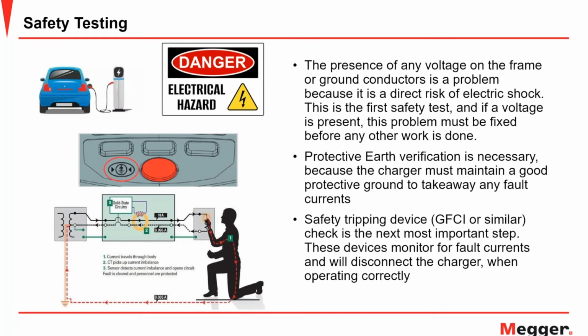Now, in itself, that protective earth verification is important, but then another layer of safety is the safety tripping device. Could be a GFCI. But in general, those kinds of devices would be monitoring the current flowing through the protective earth. And if it rises above a certain amount, like 6 milliamps, for example, then it'll trip. So for safety, you'd be testing that there's no voltage present. And if there's a protective earth and it's well connected, there shouldn't be a voltage present.